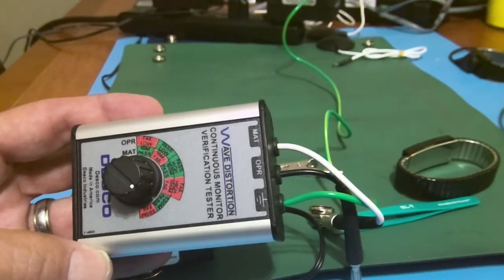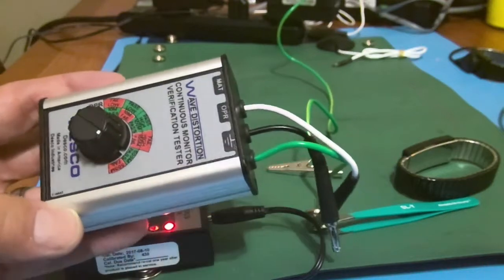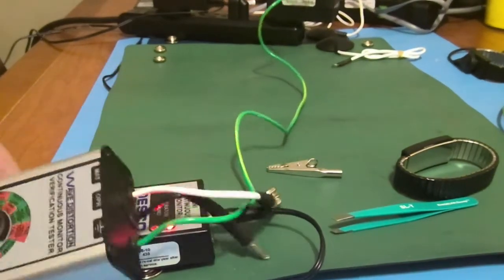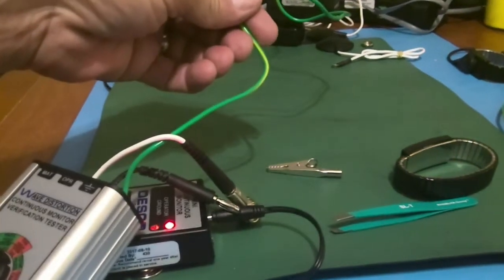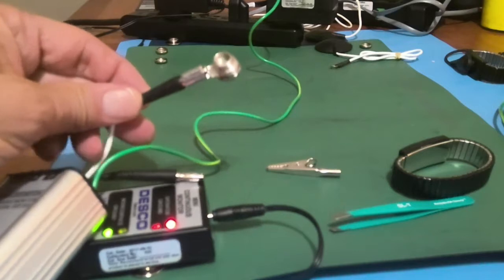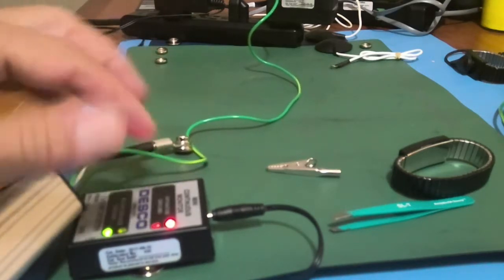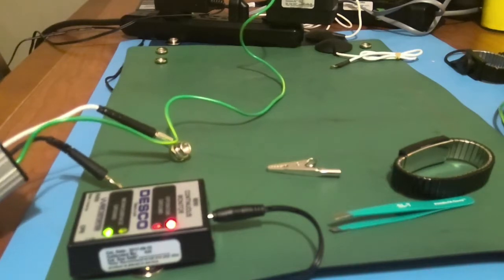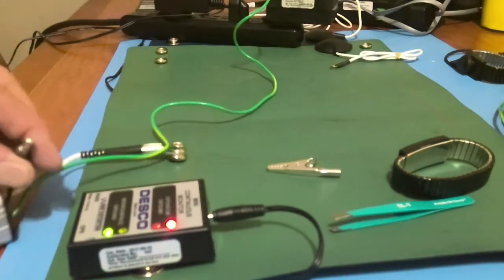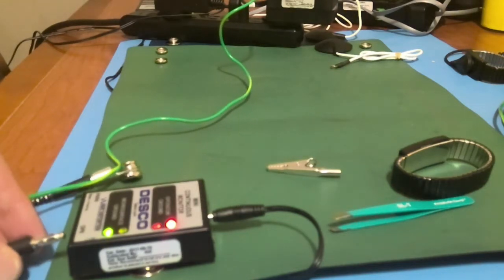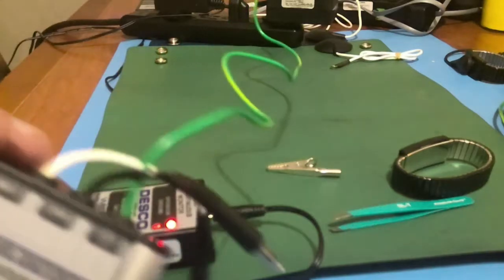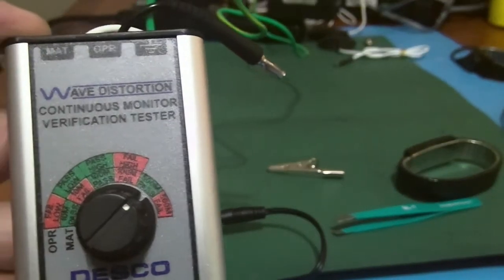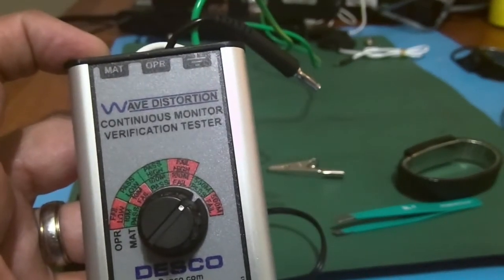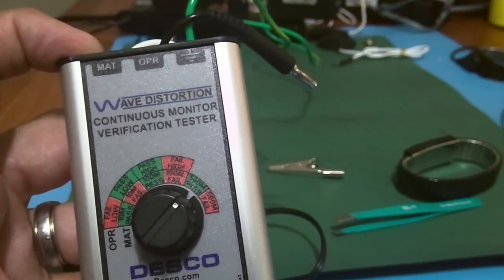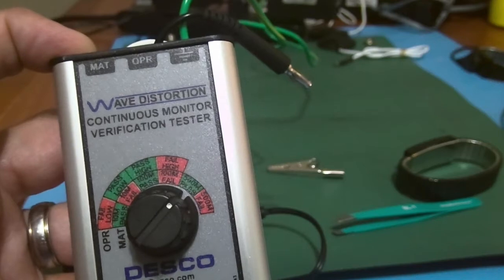Okay, so the first thing you want to do is the operator test, which is very simple. On this device, there are 3 leads. One is a green wire. It's going to go to ground. One is a white wire. This is going to be used to test the mat circuit, because this monitor also monitors the connection of the mat to ground. And then the black wire is the operator test. So if we take this dial, and you'll see there are 4 settings for the operator: a fail low, a pass low, a pass high, and a fail high.